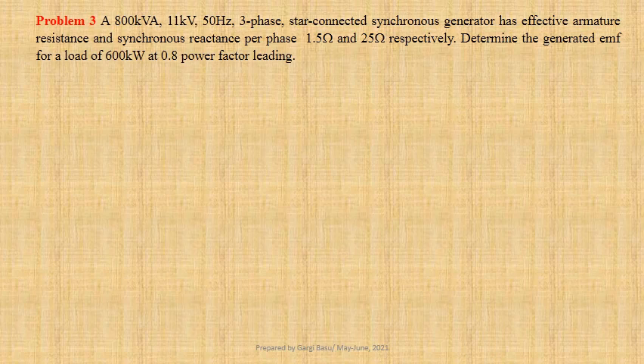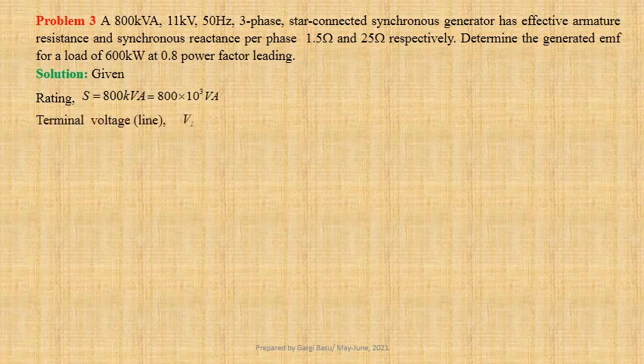Let us first write down the given data. Rating of the generator S equals 800 kilovolt ampere. That is equal to 800 into 10 to the power 3 volt ampere. Line to line terminal voltage VL equals 11 kilovolts. That is equal to 11,000 volts.